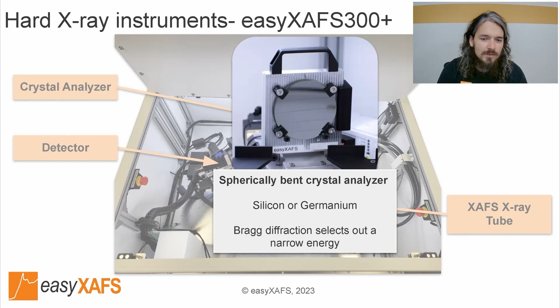The next key component is the spherically bent crystal analyzer. This is at the heart of every EasyXAFS instrument. Similar to a prism for optical light, using Bragg diffraction, the crystal analyzer selects out a nearly monochromatic energy from the broadband output of the X-ray tube. The crystals can either be silicon or germanium, and by using different orientations for the crystal wafers, we can measure different energy ranges.